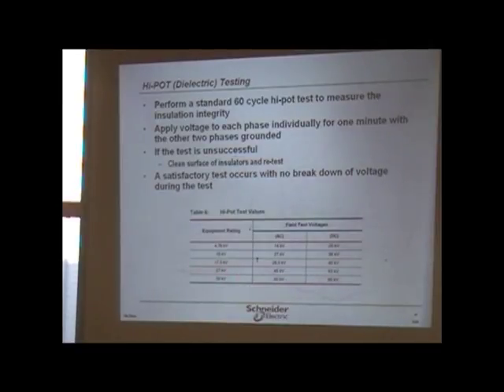So that's why I said a general rule of thumb, if you don't have this that you can't remember, go 2.5 times, you can't go wrong. Because you're going to be approximately right in that range between the two, almost like the other. So it's not going to hurt anything really per se. But you're making sure, more than anything else, importantly, that the equipment is going to be able to hold that rating at 2.5 times.